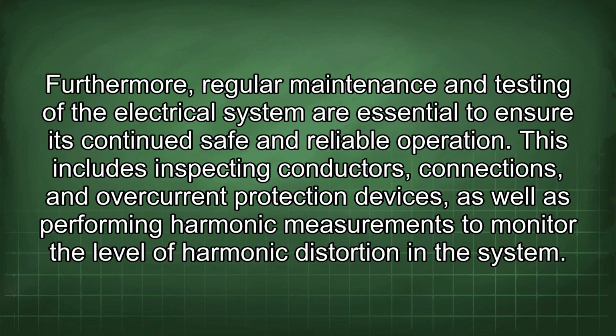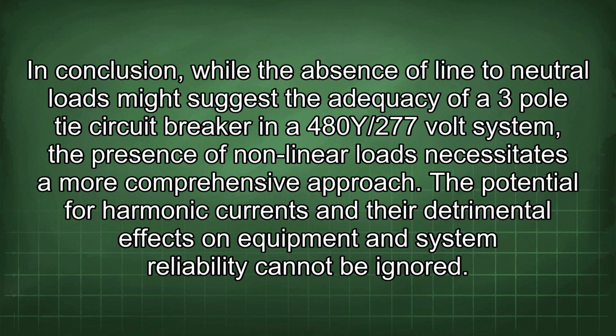Furthermore, regular maintenance and testing of the electrical system are essential to ensure its continued safe and reliable operation. This includes inspecting conductors, connections, and overcurrent protection devices, as well as performing harmonic measurements to monitor the level of harmonic distortion in the system. In conclusion, while the absence of line-to-neutral loads might suggest the adequacy of a 3-pole tie-circuit breaker in a 480Y/277V system, the presence of nonlinear loads necessitates a more comprehensive approach. The potential for harmonic currents and their detrimental effects on equipment and system reliability cannot be ignored.